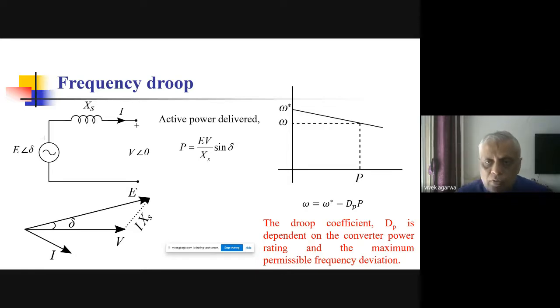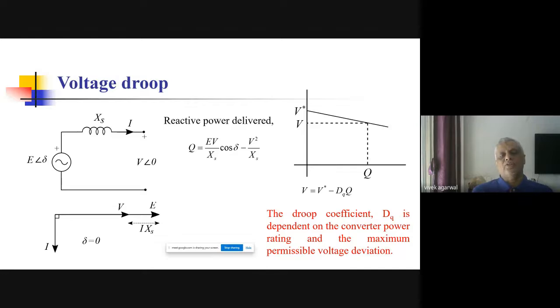The information about the frequency has to be fed to the generating system, and then depending on the slope of this, it decides what active power it must supply to the bus or to the system, and prevent the unequal sharing. So all the generating systems use this droop control, and this, remember, is inherently present in the conventional system because of the synchronous generators, because of their inertia. Some of these things are automatically there. But in microgrids, where the inertialess systems are there, where power electronics is used, with no inertia, this has to be incorporated externally into the control of the inverters or converters which are interfaced with the microgrid bus. You can see here the second part of the droop.